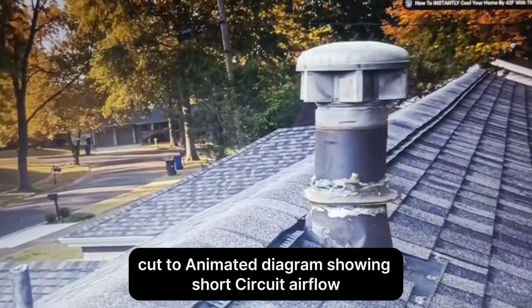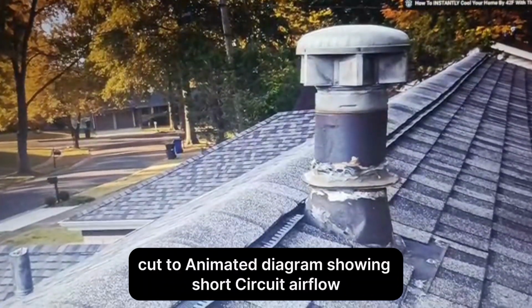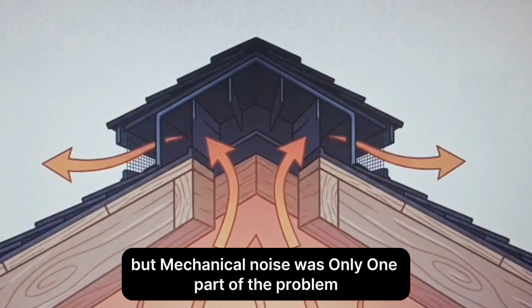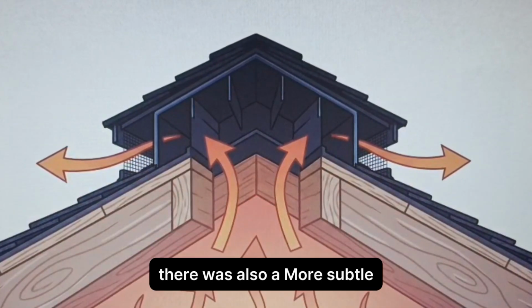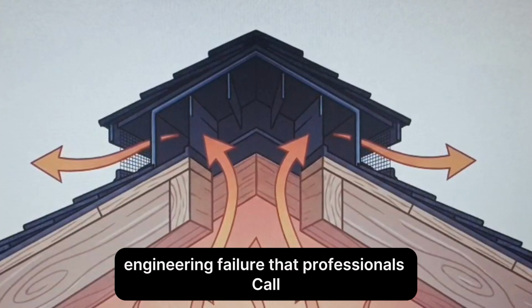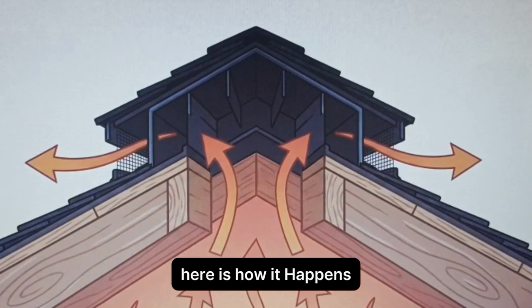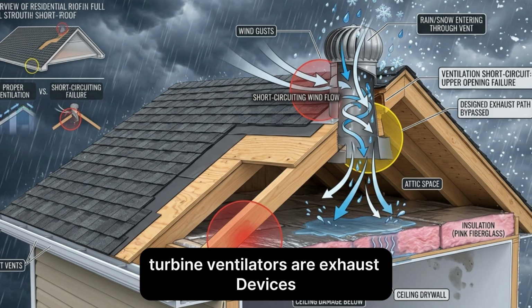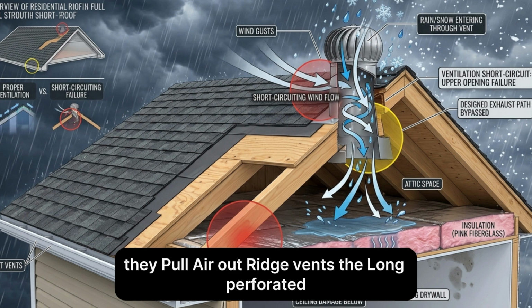Cut to animated diagram showing short-circuit airflow. But mechanical noise was only one part of the problem. There was also a more subtle engineering failure that professionals call short-circuiting. Here is how it happens. Turbine ventilators are exhaust devices. They pull air out.